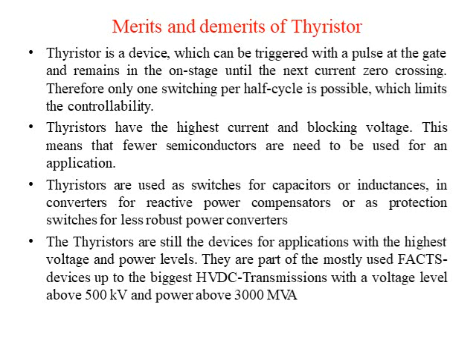In order to increase the controllability, GTO thyristors have been developed, which can be switched off with a voltage peak at the gate. These devices are nowadays replaced by integrated gate-commutated thyristors, so IGCT, which combines the advantage of the thyristors, the low on-state losses, with low switching losses. These semiconductors are used in smaller FACTS devices and drive applications.